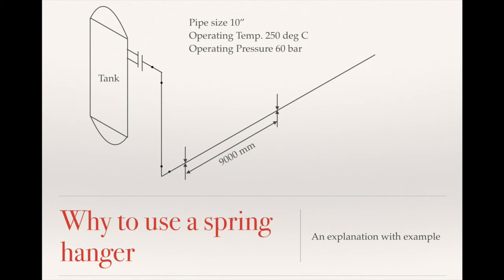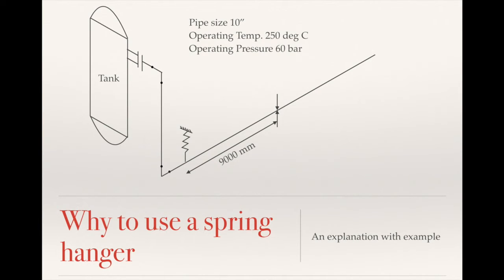Normally, if we forget about a spring, we need to support this pipe. Based on experience, we put supports with a span of 9 meters. But in this leg there will be a large amount of thermal expansion due to the operating temperature. The pipe will try to expand, but due to the support it cannot, and all the force goes onto the nozzle. So we need a device that can support the pipe and at the same time allow thermal expansion — and that's the spring hanger.